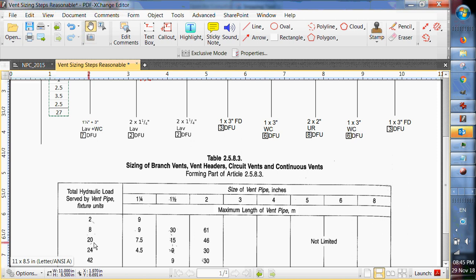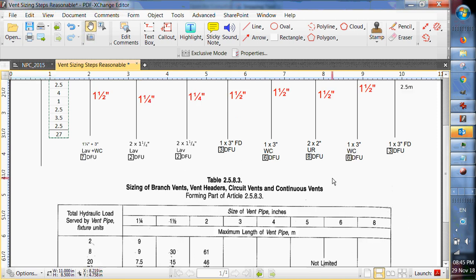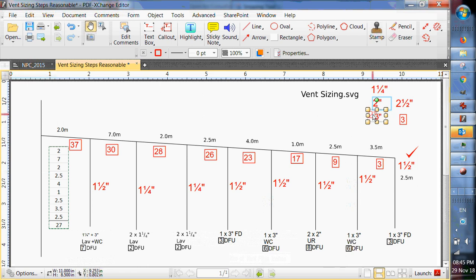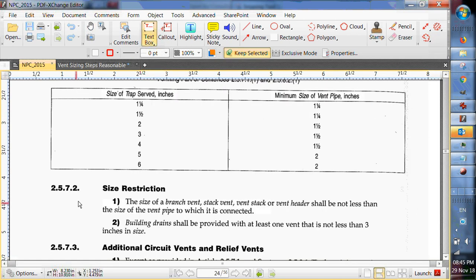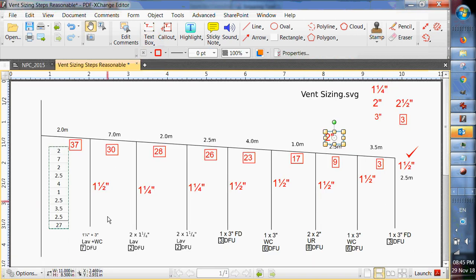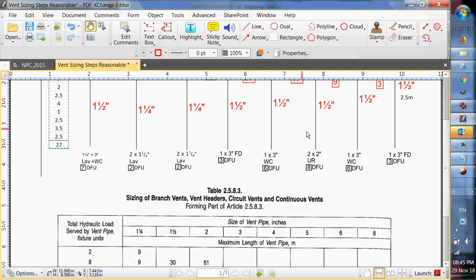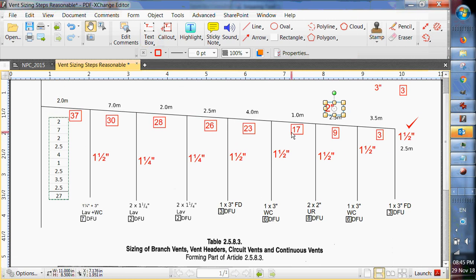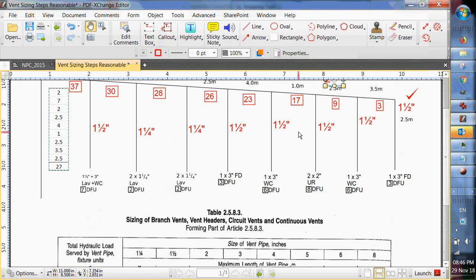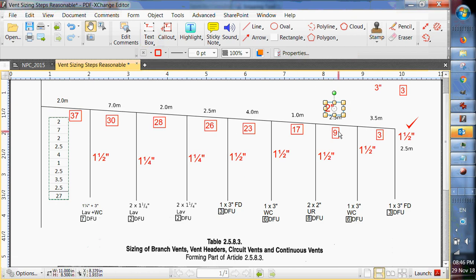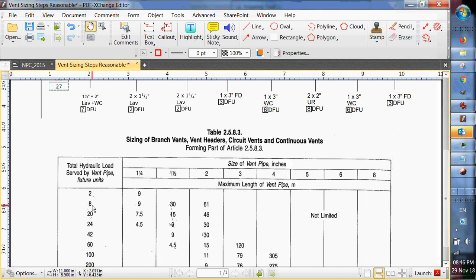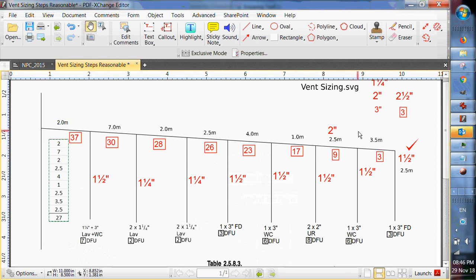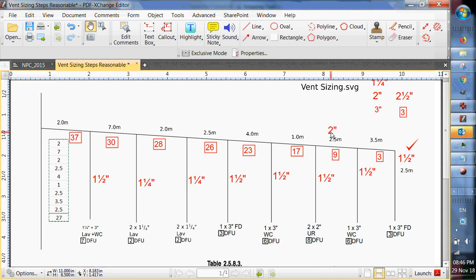Two inches good up to 20 fixture units. Now I'm forgetting where we were. Was that nine that we were working on? 17. 17 would bring us up to there. Nine. Yeah, nine. It's the nine we were working on. So nine is going to get us to here. And we're going to have to upsize it to two inch at the nine fixture units. So that's what we did. We couldn't use inch and a half. So we're inch and a half from there to there. Two inch between those two.